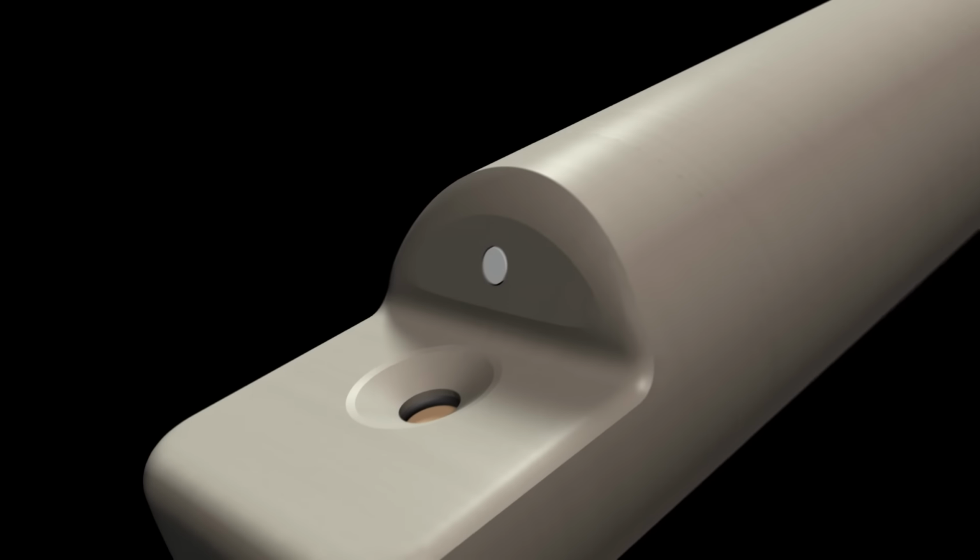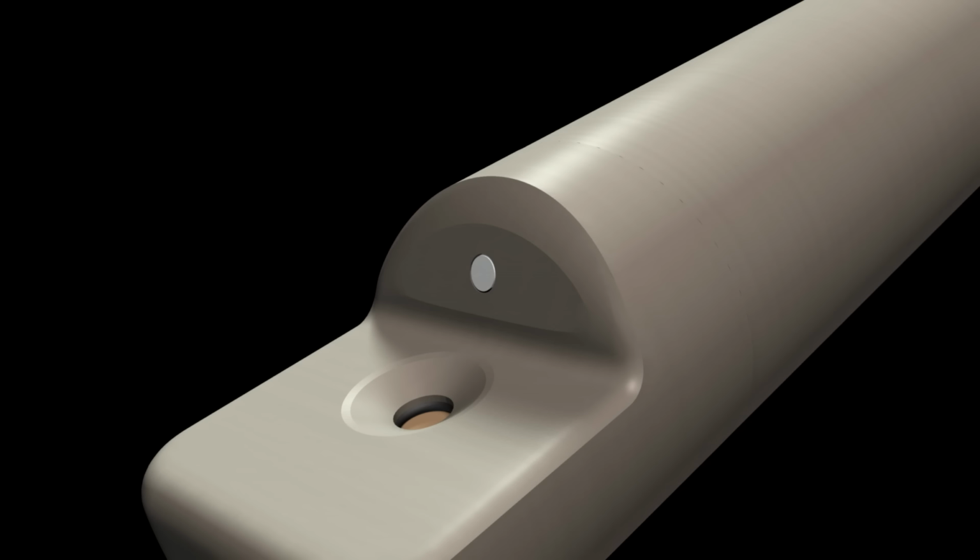Just like the glass sensors, the ISFET sensor also needs a stable reference potential. The potential that forms at the ISFET can then accurately be measured against it. The reference system is also protected from the measured solution by a so-called junction.